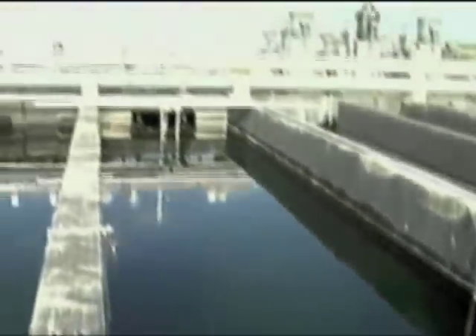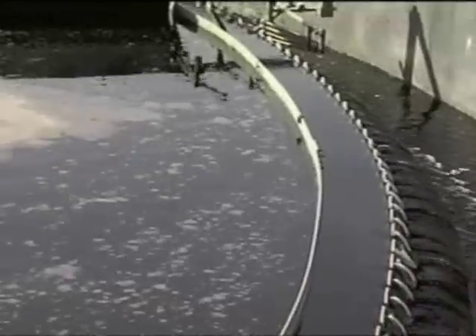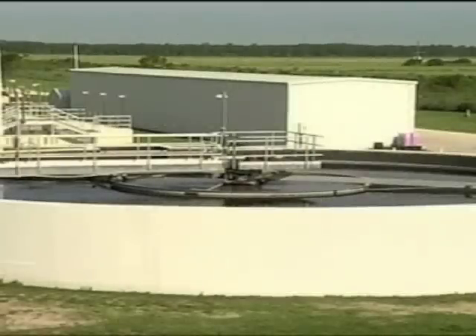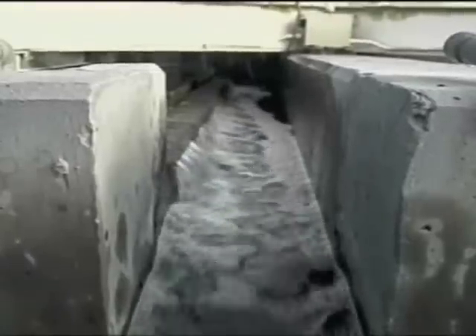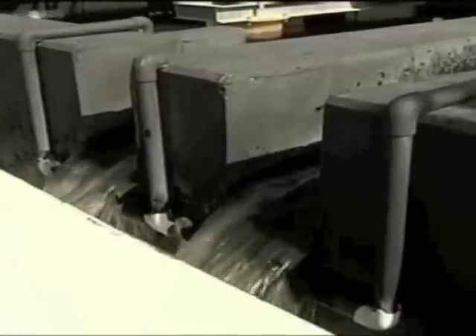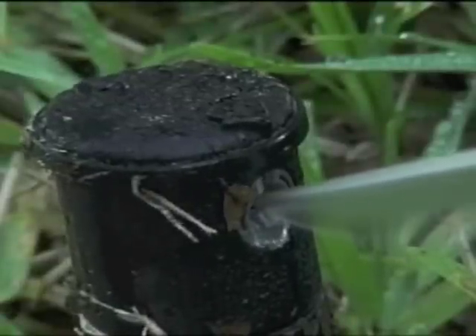In order to prevent pollution in the river, the treatment technology was upgraded to biological nutrient removal — advanced waste treatment. This technology uses naturally occurring bacteria to treat the sewage in a manner similar to composting. Manipulation of dissolved oxygen levels in the wastewater allows the bacteria to remove pollutants in the treatment plant. At the end of the biological treatment process, the reclaimed water is filtered and chlorinated to make it suitable for lawn irrigation. Although most of the reclaimed water is used for irrigational purposes within a 24-hour period, the excess reclaimed water is stored here in the wetlands where it's polished — that is, excess phosphorus is removed from it.